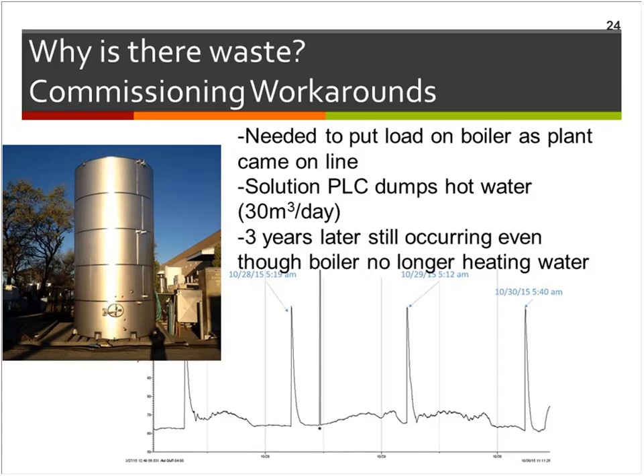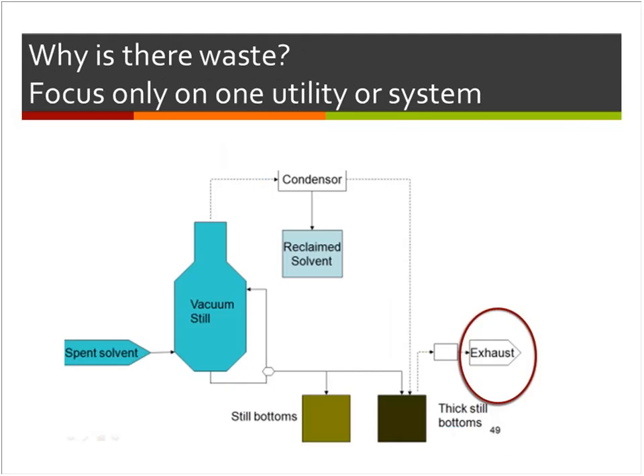Another quick example is looking only at one utility. Here's a solvent manufacturer. A traditional energy-focused approach says, if you have any exhausts, that's where your energy is going. If you only focus on a single system like that exhaust, you're typically missing the larger picture. So instead of seeing what more efficient exhaust you could have, or how to recover heat from it, we asked ourselves: why is the exhaust there in the first place?